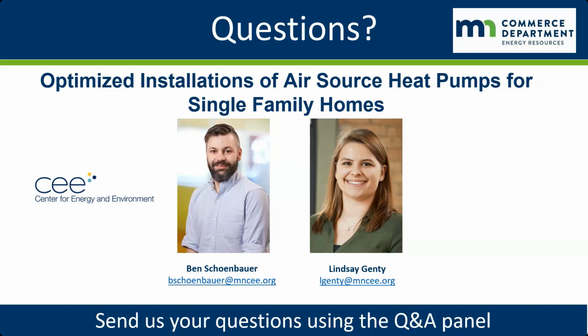The cost piece, we'll see change. It's harder to predict where costs are going to go because electric costs are ever changing. On the rate piece, I don't have the numbers right in front of me, but the emissions switchover is actually quite a bit cooler than a cost-based switchover. So I think more typically down to something like 5 degrees outside is emissions positive for the heat pump. But like I said, it depends on how clean your electric grid is and how efficient your heat pump is.